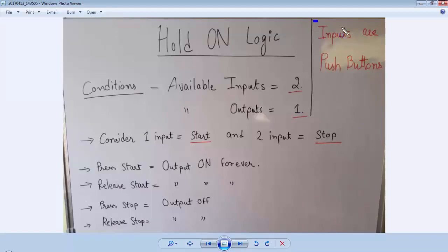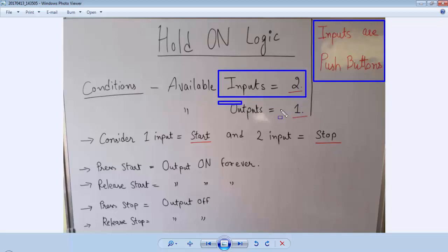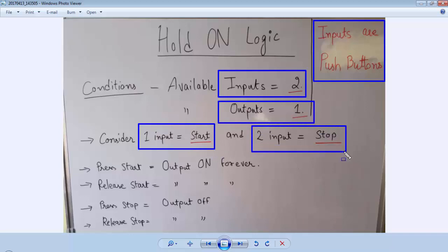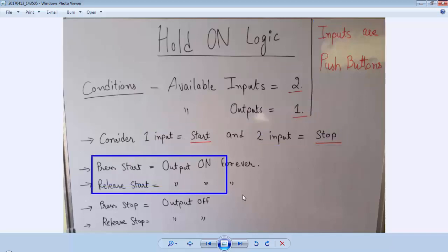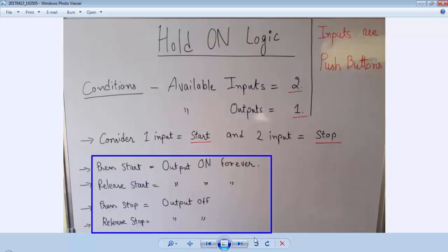For a hold on logic, first you have to consider that all the inputs are push buttons. We need two inputs and one output — one input as a start button and the second as a stop button. For the initial condition the output will be off. Press the start button to turn on the output, and even after releasing the start button the output should remain on. To turn off the output you press the stop button, and even after releasing it the output should remain off.